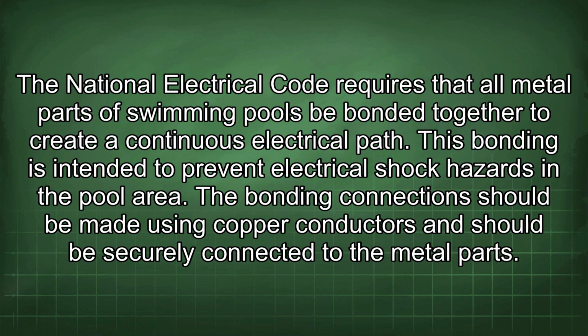The National Electrical Code requires that all metal parts of swimming pools be bonded together to create a continuous electrical path. This bonding is intended to prevent electrical shock hazards in the pool area. The bonding connection should be made using copper conductors and should be securely connected to the metal parts.